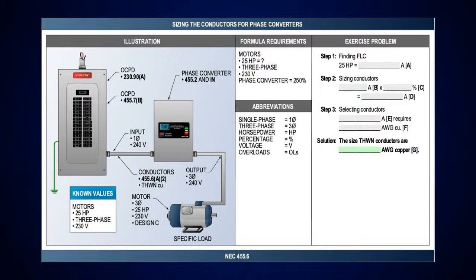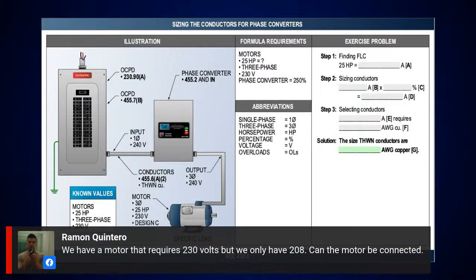And I'm going to do this off the top of my head, okay? Because I don't have the table right in front of me here. I don't have my code book out. I usually do all this off the top of my head. So when you get over there, it'll tell you right where it has the horsepower on the left-hand side. It talks about the full load current values, and what is typical for those motors running at those speeds, okay? And then it'll have the currents that are listed shall be permitted for system voltage ranges. This is where you want to look at this, okay? And what did he say? He had a 208 volt? Is that what he said? No. So I've actually run into this before, a 230 volt motor, and they only have a 208 three-phase.